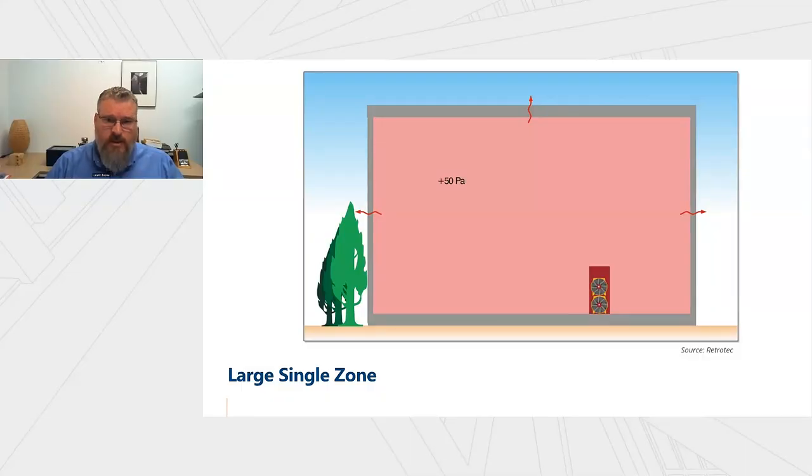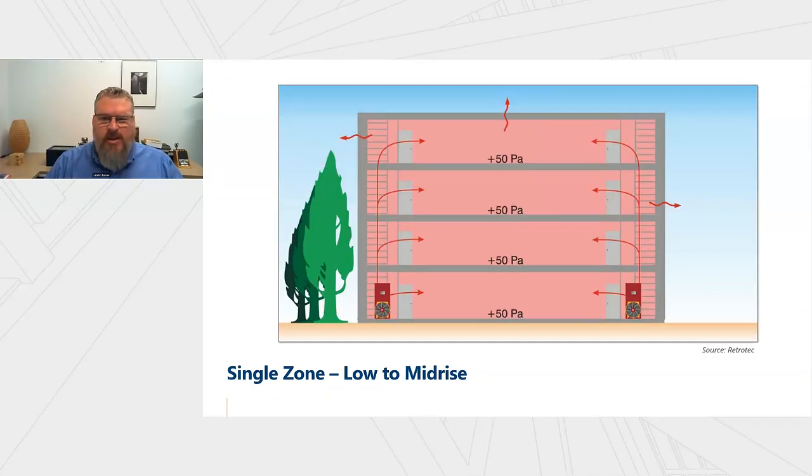to one constant pressure. In reality, most buildings that get tested look a little bit more like this, whether they're multifamily, residential or commercial office buildings. Usually you're going to deliver the air at the bottom, as long as there's not too much stack effect that you're fighting. And the air is going to go to the different floors, usually via stairwells and their doors.